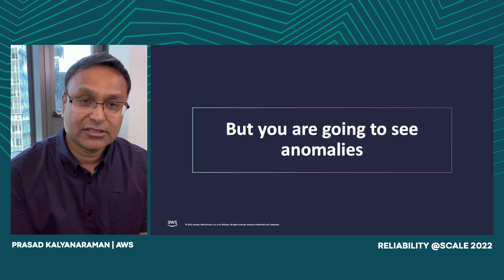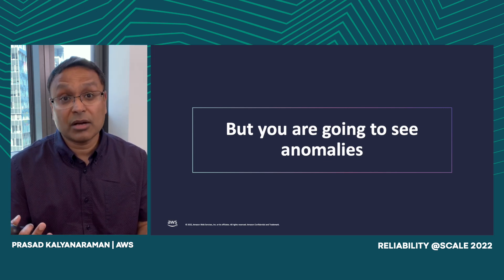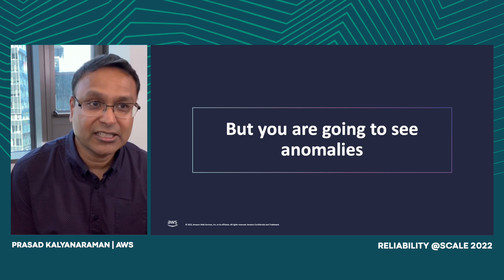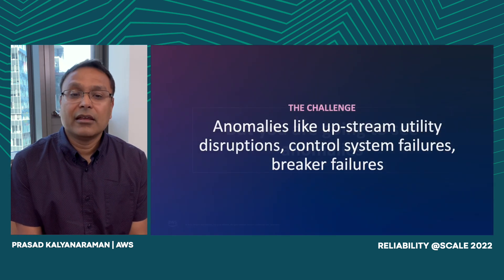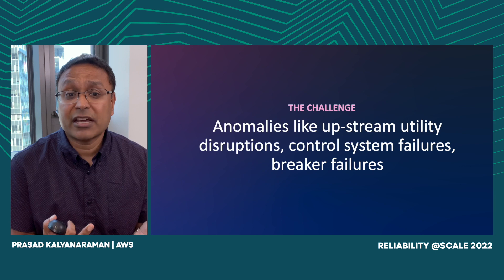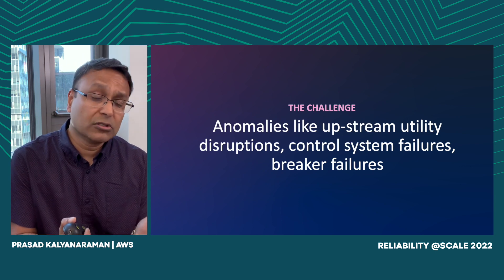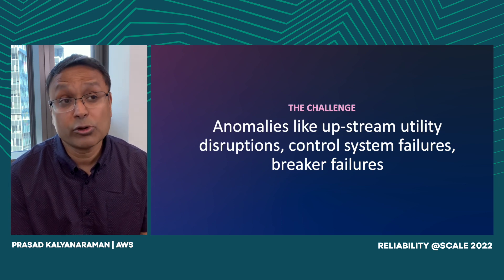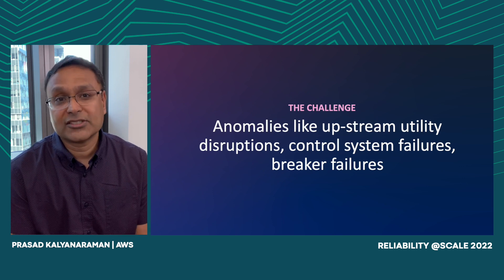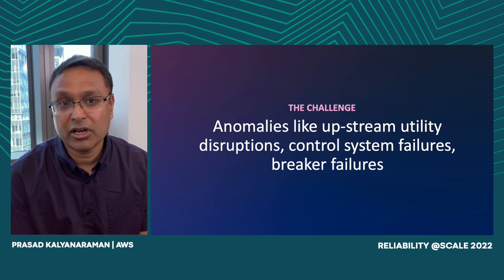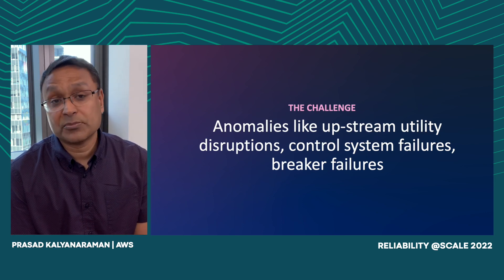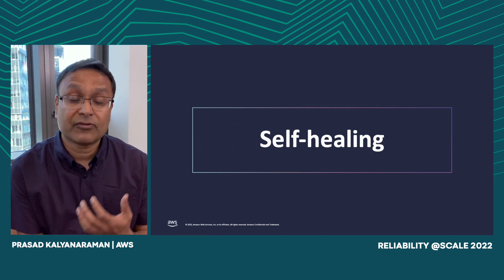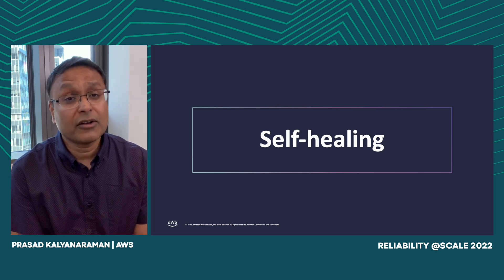You're going to see anomalies in your production environment. You can design for many of them, but at some point you'll be caught by an anomaly you've never seen before. These can include upstream utility disruptions with unusual power signatures, control system failures, breaker maintenance failures, and oversubscription events when servers consume a lot of power on single lineups. We've built self-healing systems to recover from these anomalies automatically, and that has paid significant dividends.